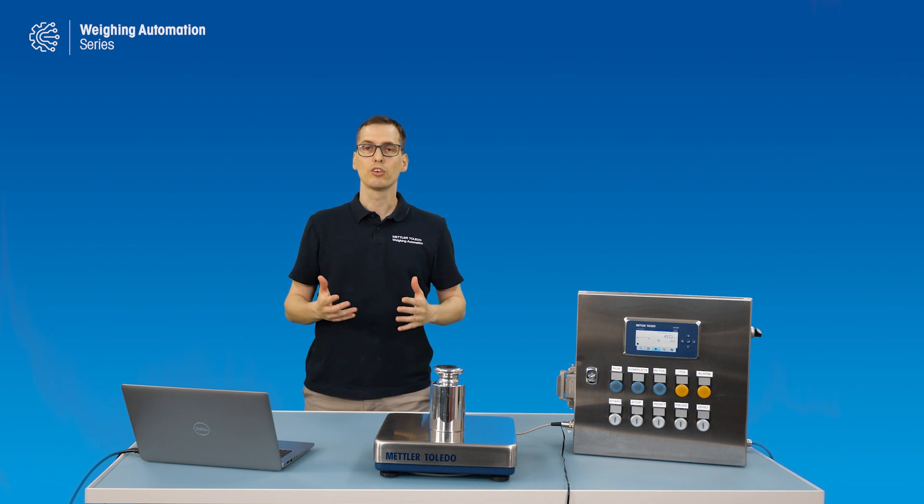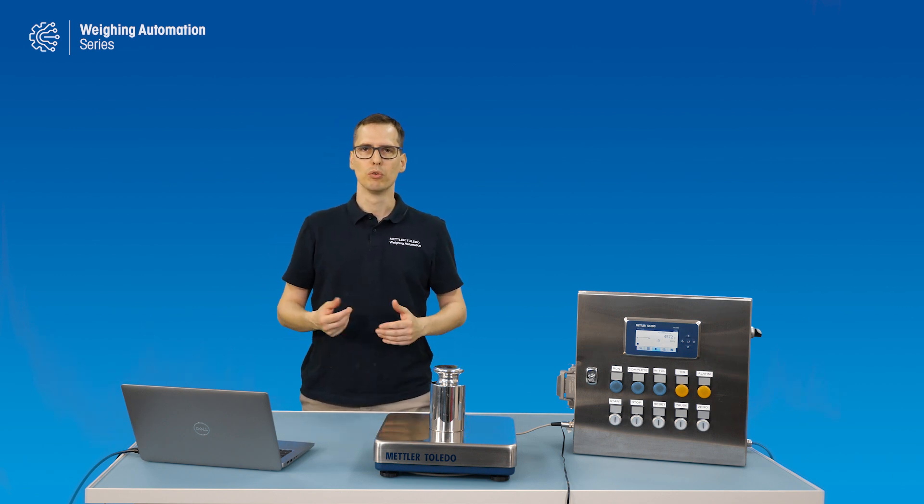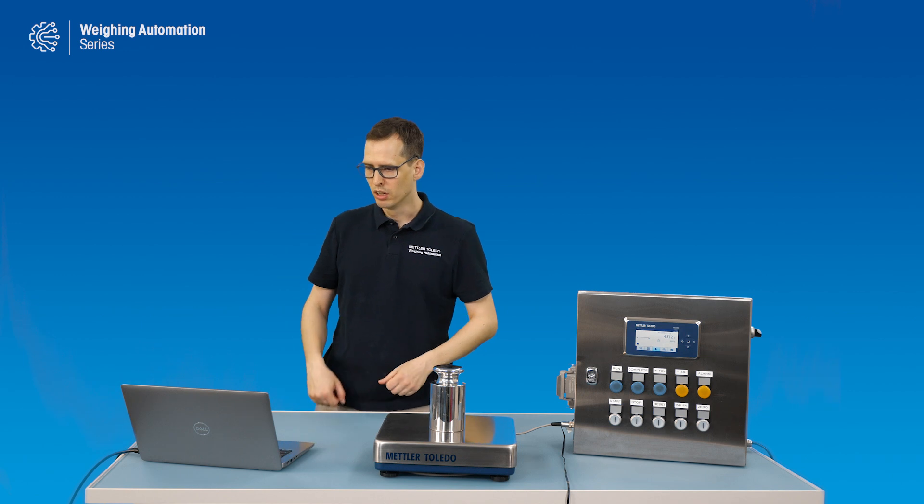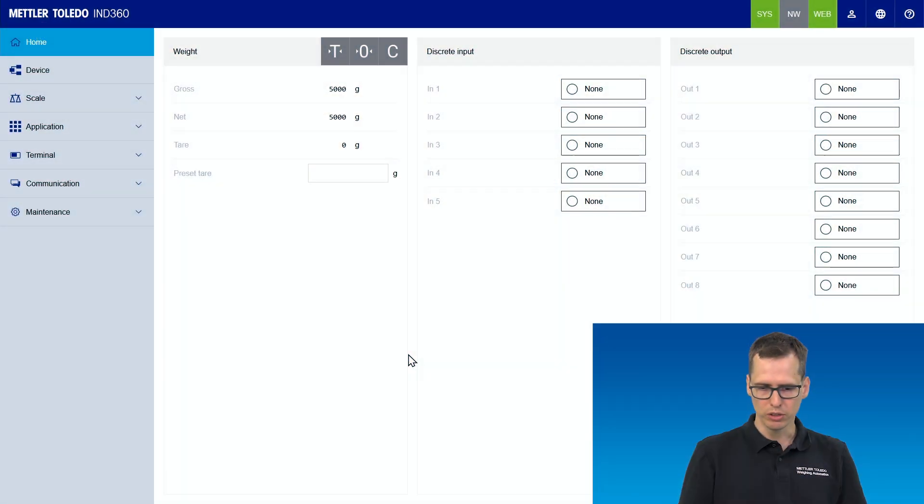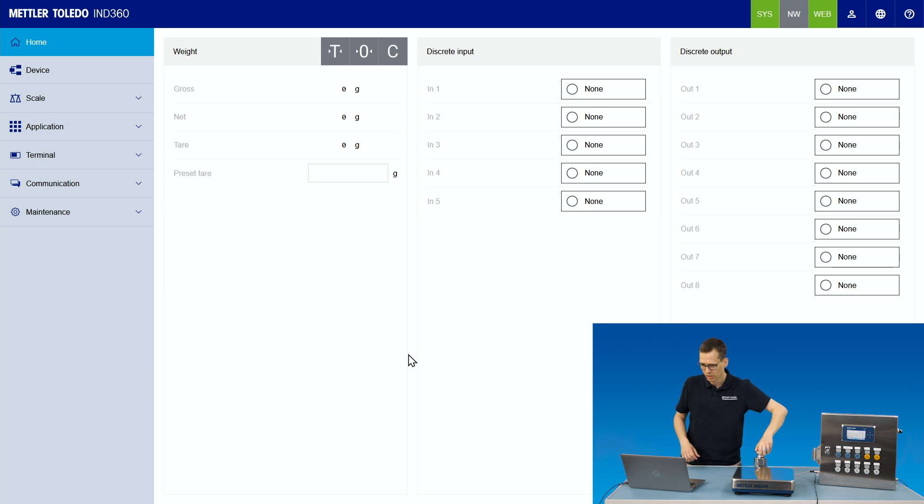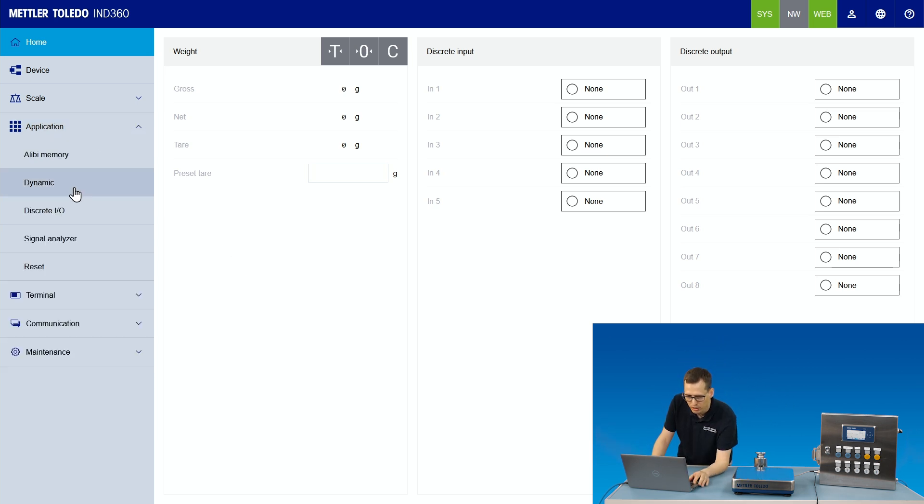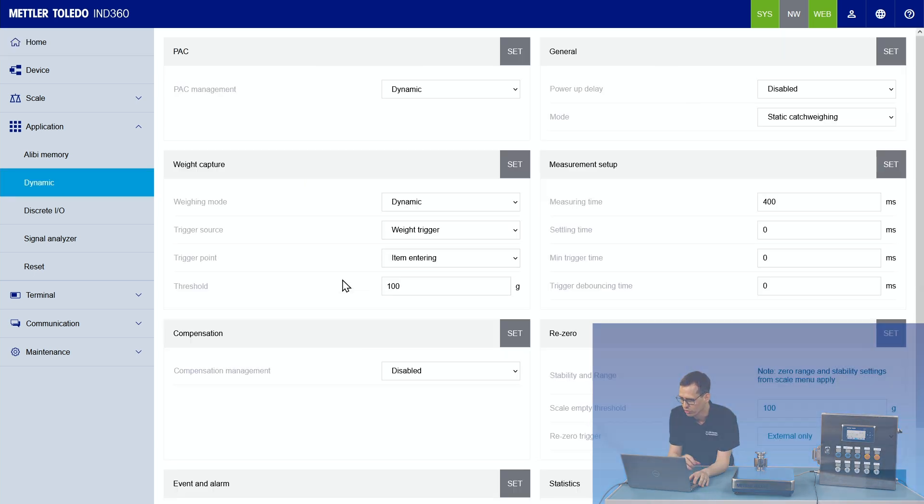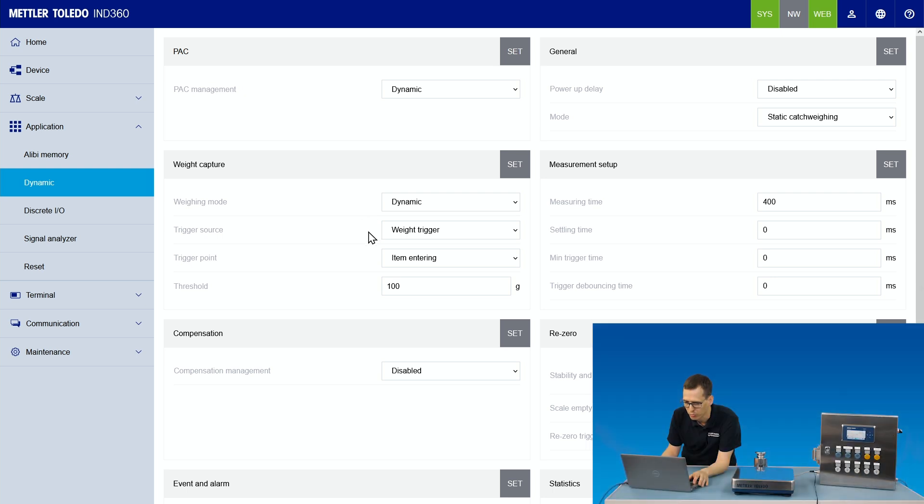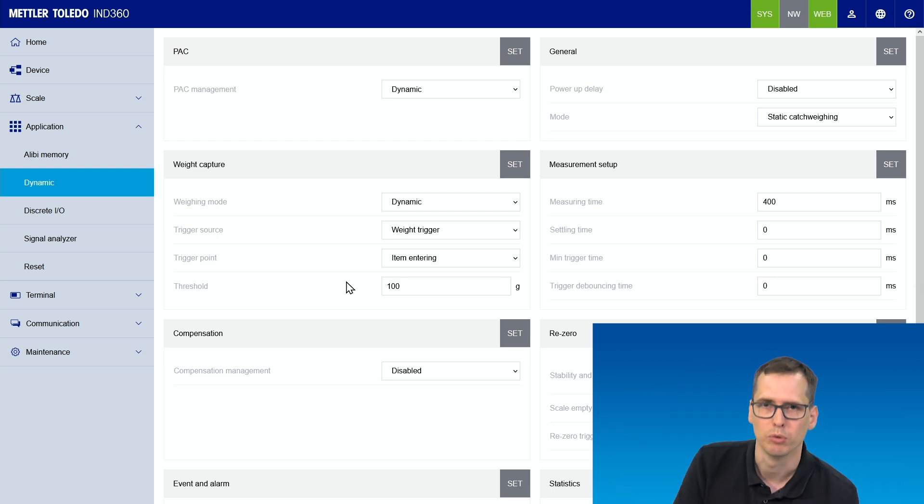So let's configure and tune the system together for dynamic static weighing. Looking at the web interface, we see we still have 5 kilograms on the scale. I'll remove that. And then we go to application, dynamic, to look at the parameterization. I already configured static catch-weighing as a mode. This is what we want to do. We capture the weight while it's still in motion and we use a weight trigger. So meaning if the weight exceeds 100 gram, it will trigger a weigh-in operation.